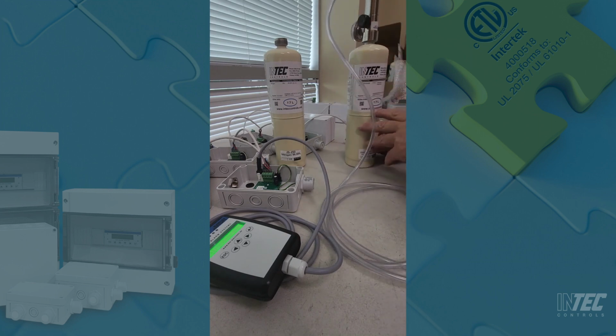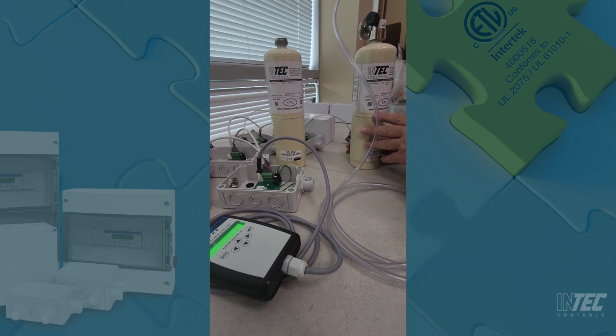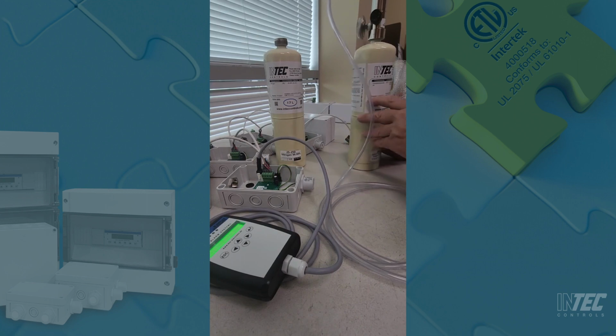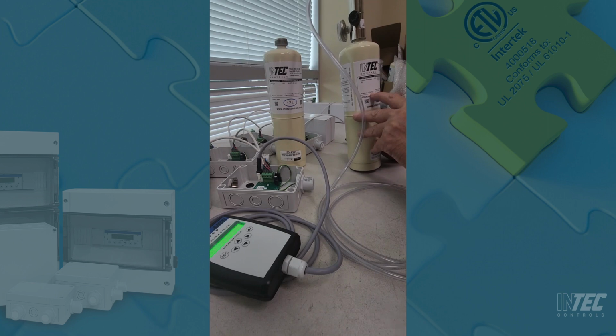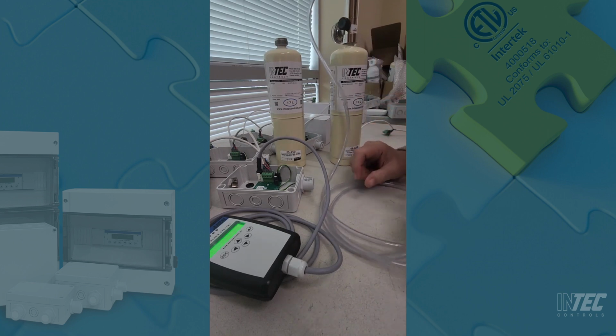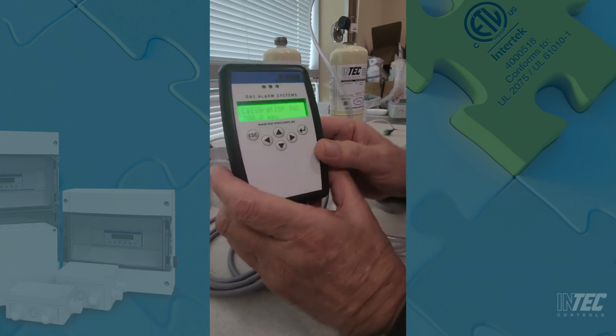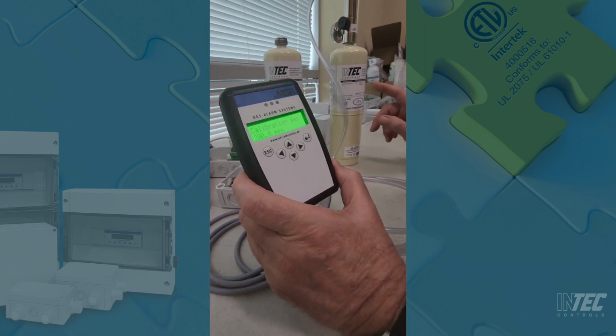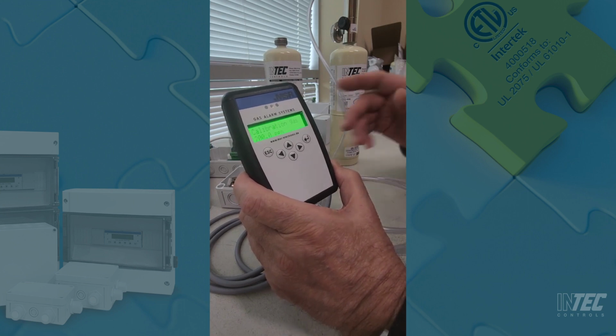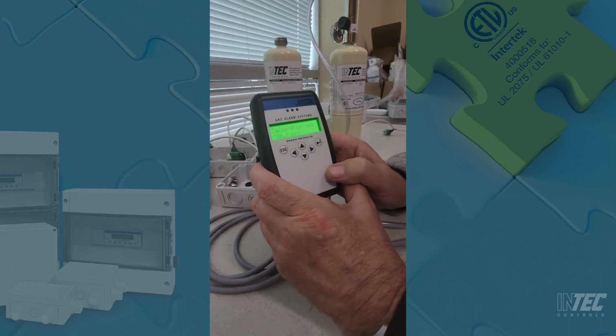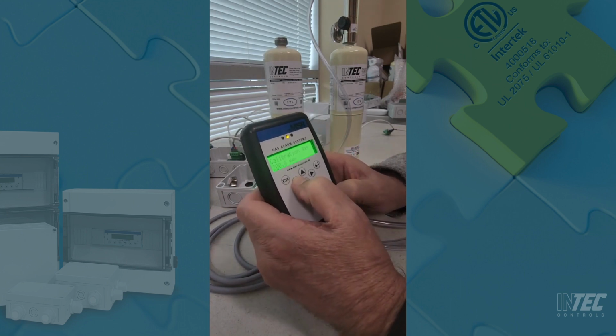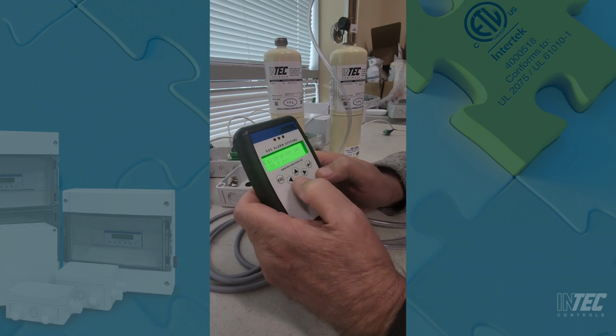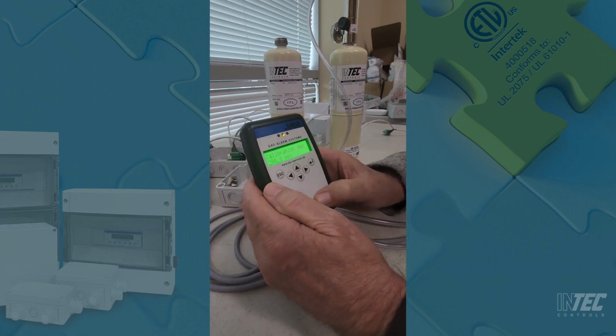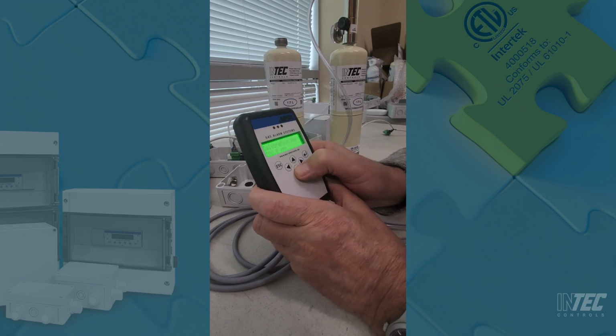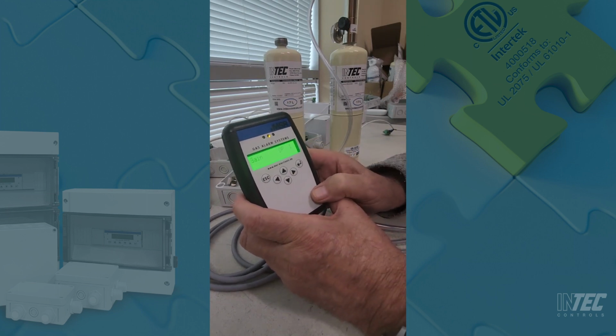Before you calibrate, you want to make sure that the expiration date on your gas is still valid. There is an expiration date on the bottle. Just read on the bottle. It'll tell you when. Here's the expiration date, 11/6/2027 for this bottle of gas. So now we need to set the gas to what ppm you're using. If you hit the enter button, it's already set to 200 here. But you could change the value. If you were using 100, you would just go here and choose 100, but we're using 200. So we're good to go there.